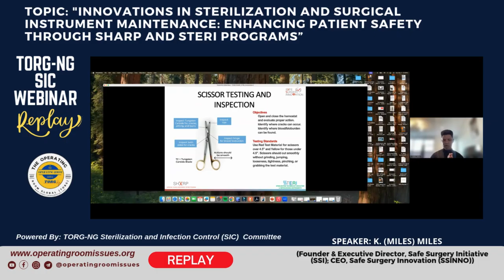So then you want to go down and make sure that you have a smooth action, which is the opening and closing. If a scissor is too loose, then it won't cut properly. If it's too tight, then it's going to cause a lot of hand fatigue for the surgeon, and it's going to grab tissue instead of cutting the tissue. So we always want to make sure that we're going through each one of these inspection points.